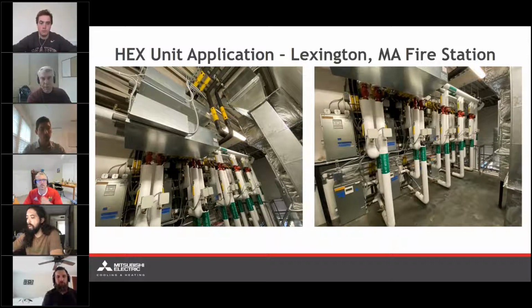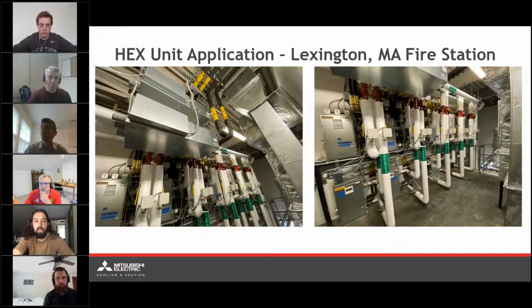Mike, it looks like you have, after these heat exchangers, can I call them just heat exchange units? Sure. Is there a refrigerant-to-water heat exchange? So then downstream of that, you just have a two-pipe system. What's nice is that you have branches of a two-pipe system and a shared plant, but you're not tying everybody together, because of the branch controller and the heat exchange function of the branch controller. The building can be in multiple modes at once. It can be heating on one side, cooling on the other. It's not locked together to one central plant. That's correct.